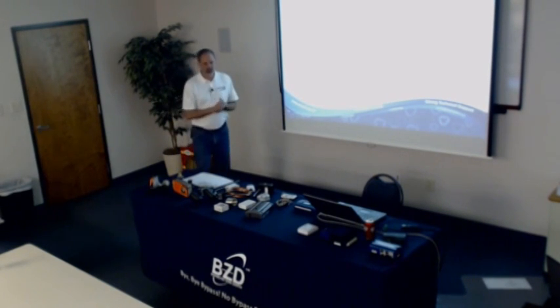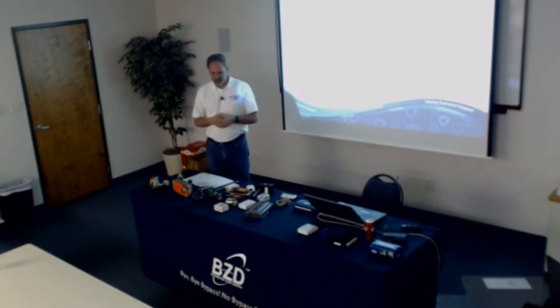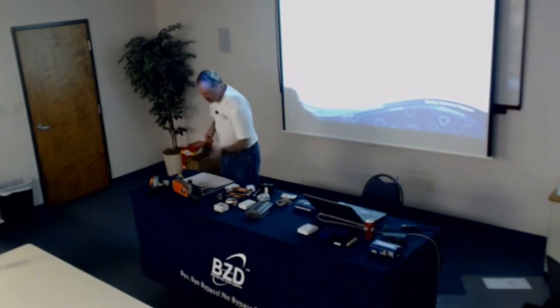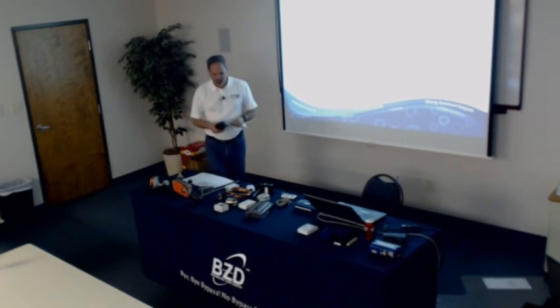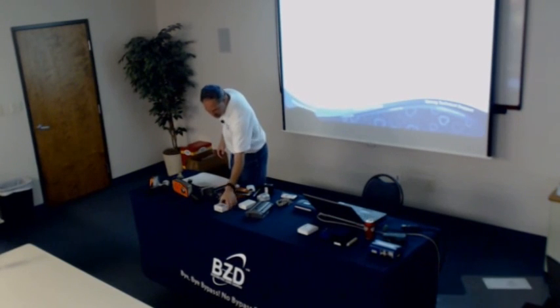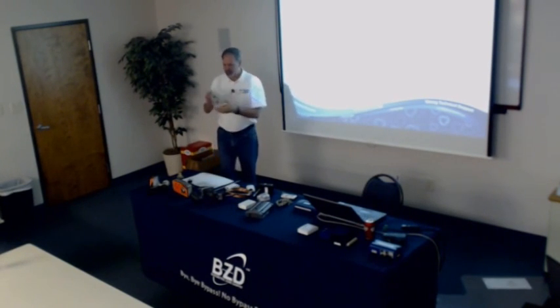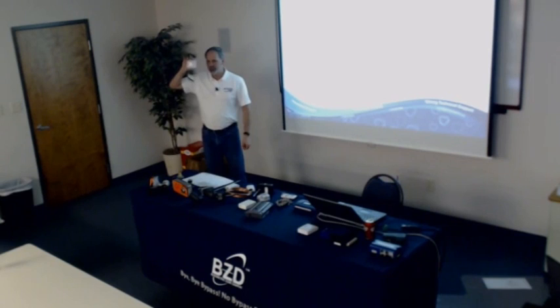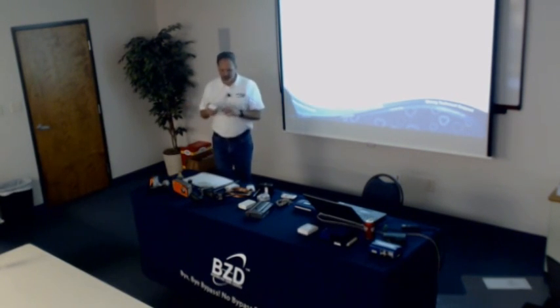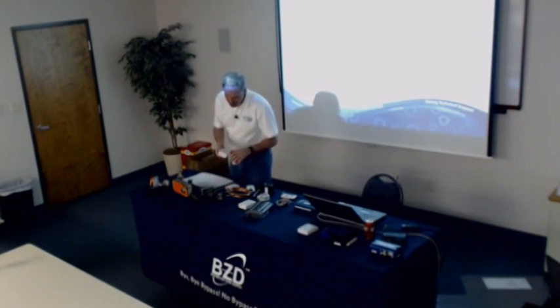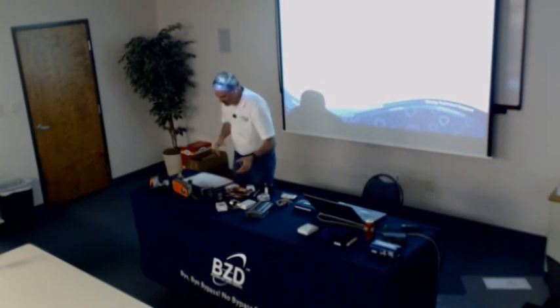And all of these sensors come in two basic types. They have analog sensors, which is what this guy is. It's a resistance. It changes all up and down. Where this guy here is a digital input. It's just on or off. If it drops below 38 degrees, it opens a set of contacts in there. That's the end of it. That's all it does. It's just either on or off. So we would call that digital or binary.